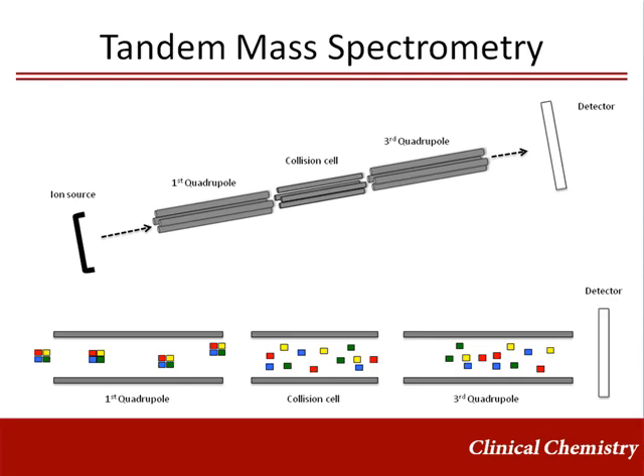Tandem mass spectrometry is a method to further enhance the specificity of mass spectrometry. Ions passed through the first quadrupole collide with inert gas in the collision cell producing fragments, and the fragments pass through the third quadrupole to the detector. Although several compounds may share the same molecular weight, and therefore the same precursor ion, they can readily be distinguished using tandem mass spectrometry if unique product ions are produced in the collision cell.